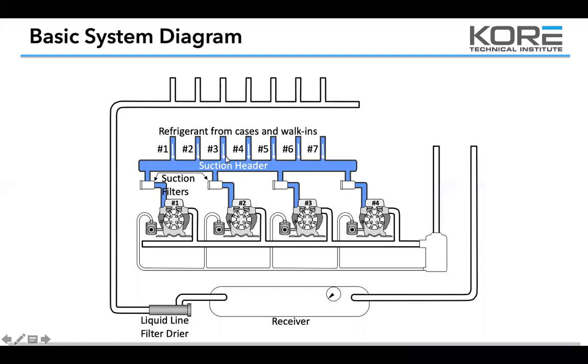On older racks that are grossly oversized, the stage four or larger compressor won't run a lot and it sometimes causes problems. Make sure when you're dealing with rack staging that you're really looking at that strategy. Look at your cycle times — you don't want stage one cycling too fast. Copeland and Bitzer both want to see that compressor cycling between six and eight times per hour, so they want to get some good run time.